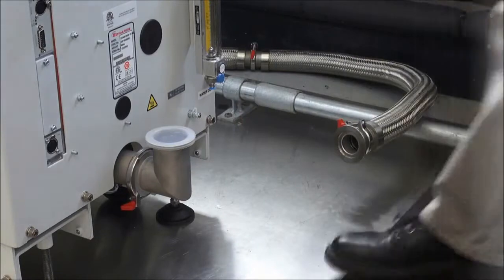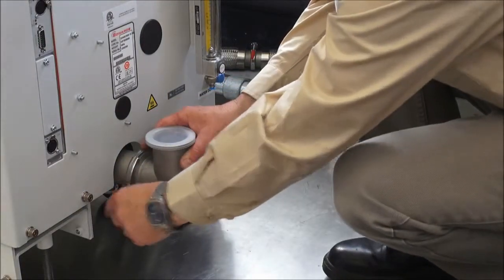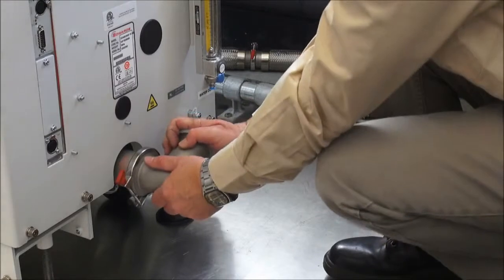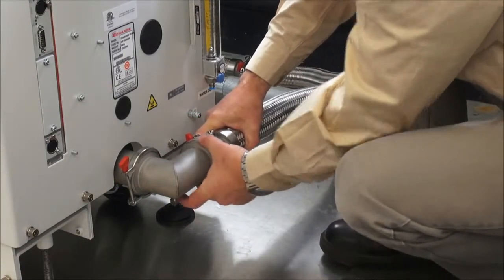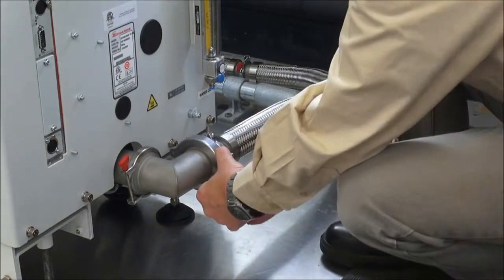The GXS exhaust outlet should be properly and securely connected to suitable rigid or semi-rigid exhaust piping. This minimizes exhaust noise and keeps exhaust gases out of the work area.